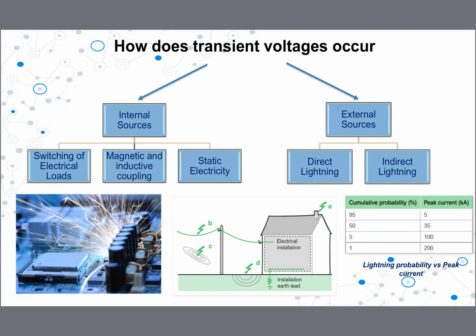As I explained, it's a highly site specific design. So you need to look at how it is installed and whether there is any chance of transferring direct lightning into the building. If there is no chance of direct lightning into the building, then you don't need to use type 1. Type 1 we mostly use to protect from direct lightning, right? So for the incoming line, there is a high chance of transferring direct lightning depending on the site condition. But if you are very sure that there is no chance of direct lightning coming in, then even type 2 is enough. That is for the indirect and switching.